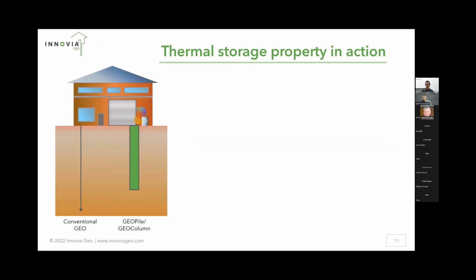And so the property that gets us really excited is this thermal storage property of the geopiles and geocolumns. And so in a conventional geothermal loop, what happens is that you're exchanging heat on a steady state basis through the surface of that pipe. With our geopile and geocolumns, we still get that effect of that heat transfer through the surface of the pipe itself. But then if the system is turned off or at a lower stage where it's below that steady state heat transfer rate, what happens is we can actually use the energy in the fluid itself and then recharge it.